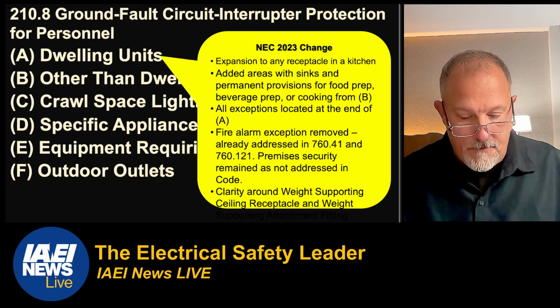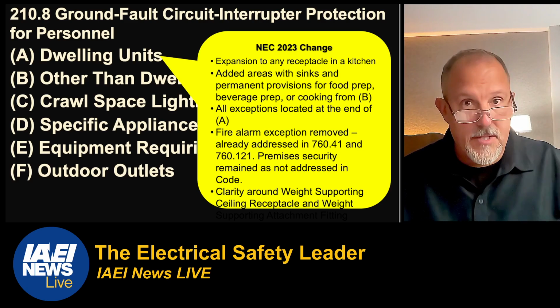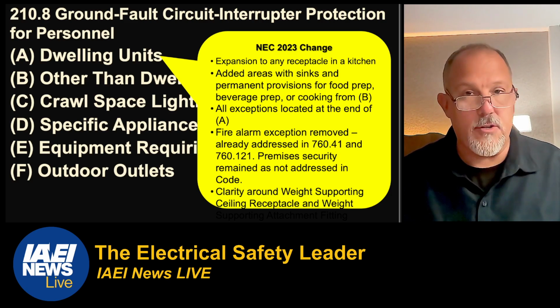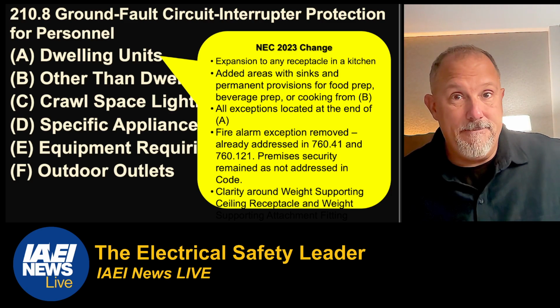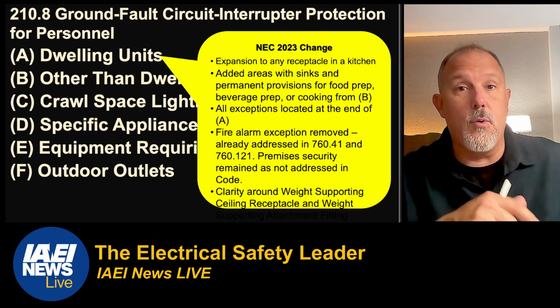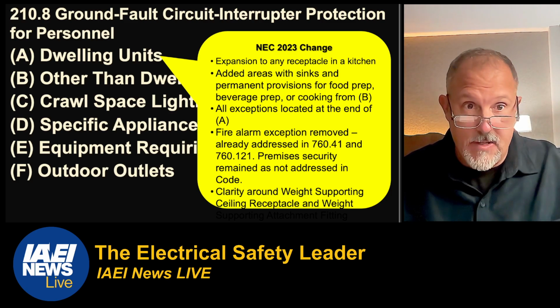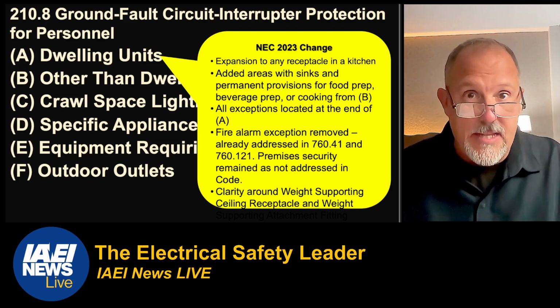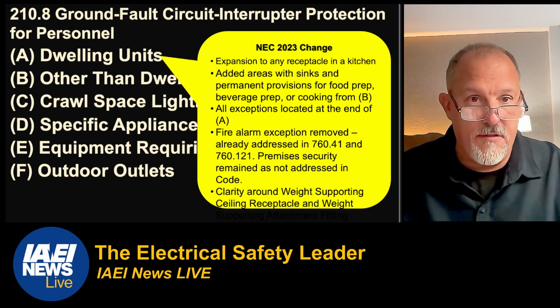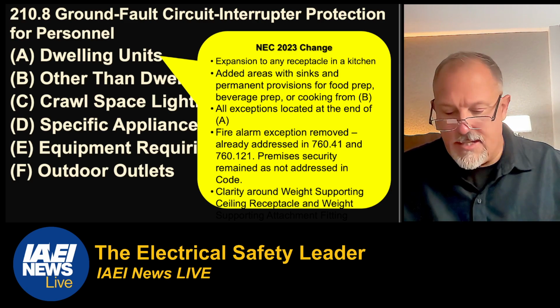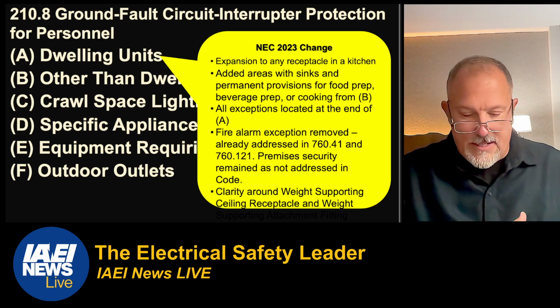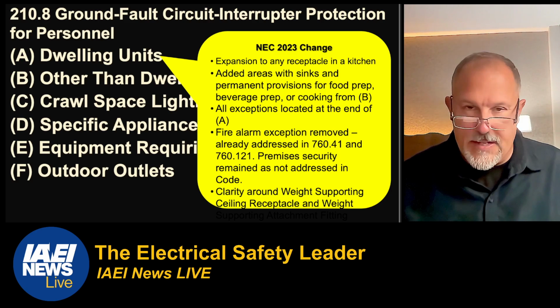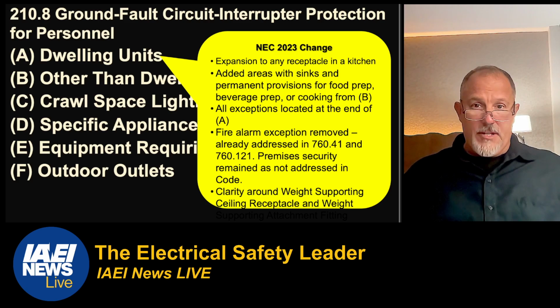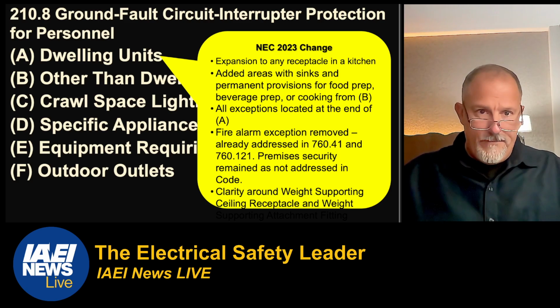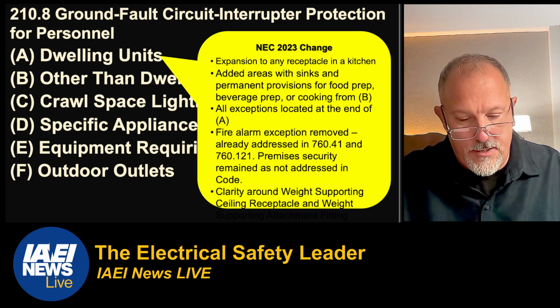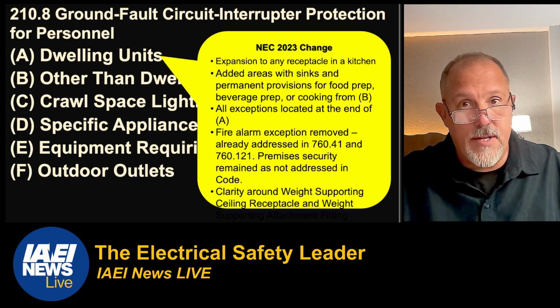So the way the exception reads now is a receptacle supplying only a permanently installed premises security system shall be permitted to omit ground-fault circuit-interrupter protection. But it's not just for basements. I don't care where that's at. You don't need to put GFCI protection for that premises security system. All right, so that's basically what we did there. Not a big change, but something that you need to be aware of. And then in the exceptions, they added some new definitions for weight supporting ceiling receptacles and then weight supporting attachment fittings. We just basically changed the terminology, and it's the same. So not as big of a deal there. So those were the changes that we saw in 210.8(A).